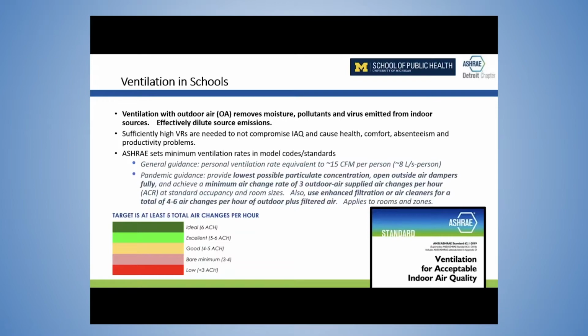In the pandemic, ASHRAE came out with additional guidance, as did other organizations. The guidance is to provide the lowest possible particulate concentrations, to fully open outside air dampers and to achieve a minimum air change rate of 3 air changes of outside air per hour. And on top of this, use enhanced filtration or air cleaners to basically double the air change rate effectively, to get a total of 4 to 6 air changes per hour of outdoor plus filtered air. Now, this applies to each classroom or other zone in the space.